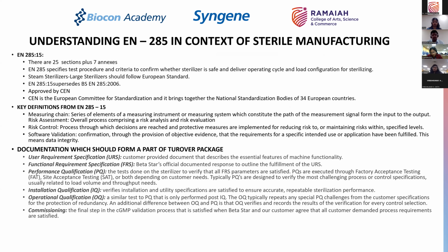This has 25 sections. It's a very interesting document to read if you get a subscribed copy of it. 25 sections and 7 annexes to the document. So it goes on to describe the autoclave guidelines very elaborately. It talks about the test procedures, the criteria to confirm whether the sterilizer is safe and is delivering the operating cycle, and the load configuration, how you should load the autoclave.